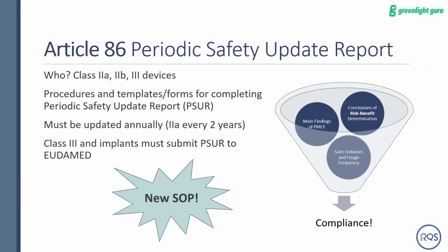Completely new is this periodic safety update report, PSUR. So this is for Class 2A, 2B, and Class 3 devices. So all new from MDR. You should have, of course, procedures and SOPs for this. It must be updated annually. So this is something you have to be on top of, like your audits or your management review. You have to make sure you're proactively updating this. For 2A, it's every 2 years, but still, this is something you should be reviewing with your quality system, make sure it's up to date for your devices.